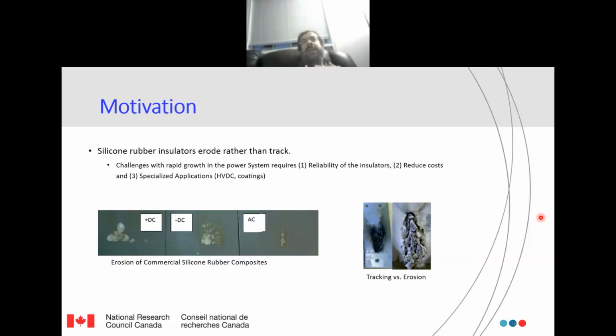And this is something very, very important: once you start to have arcing on the surface, then two phenomena will take place: tracking and erosion. Tracking is when you have a carbonized path on the surface, which will enhance even more the development of the leakage current. Why? Because carbon is a conductive material. So this is extremely bad. One of the reasons for using silicone rubber as a non-carbon based polymer is to avoid this carbonized path, this tracking. However, because of certain mechanisms, maybe Dr. Muhammad will talk about it, tracking can still happen, but erosion is the main thing that happens in silicone rubber. The material just erodes from the surface without the tracking, and mainly we were testing the erosion ability of silicone rubber.